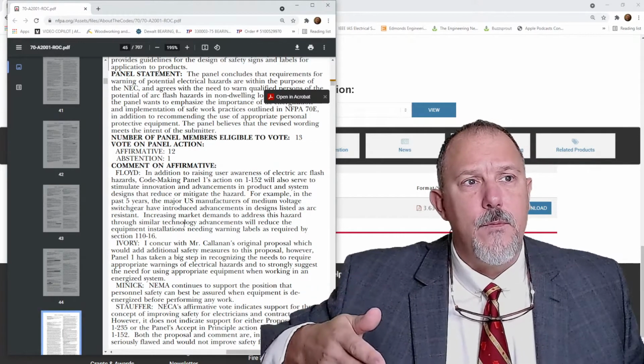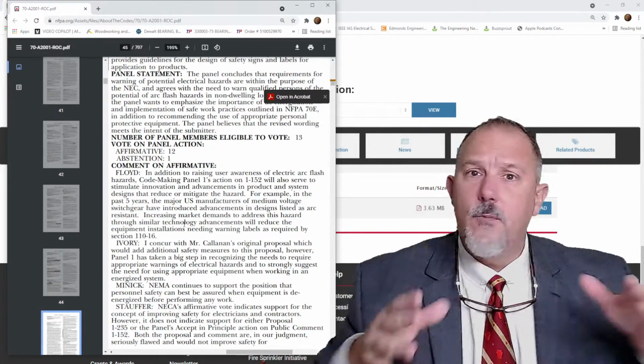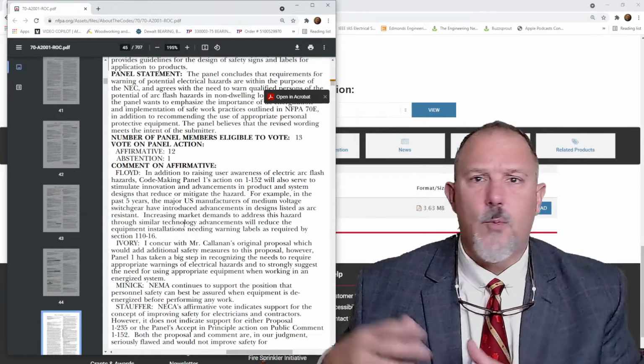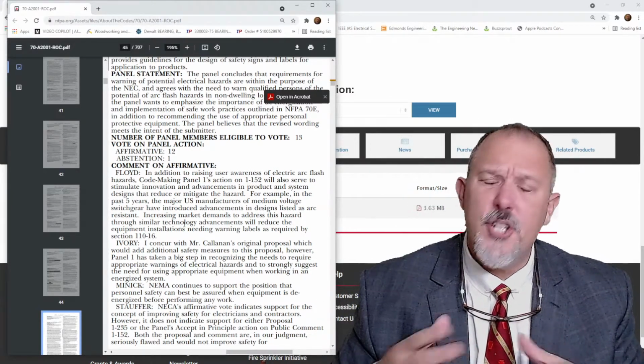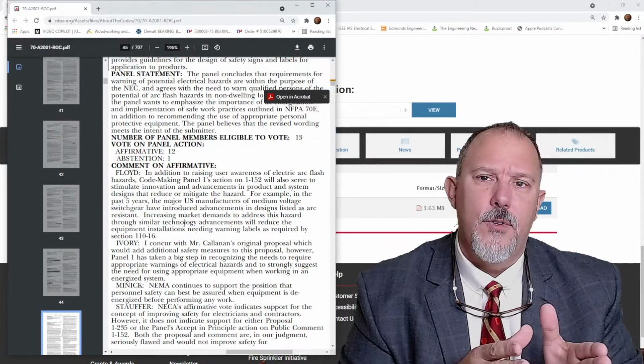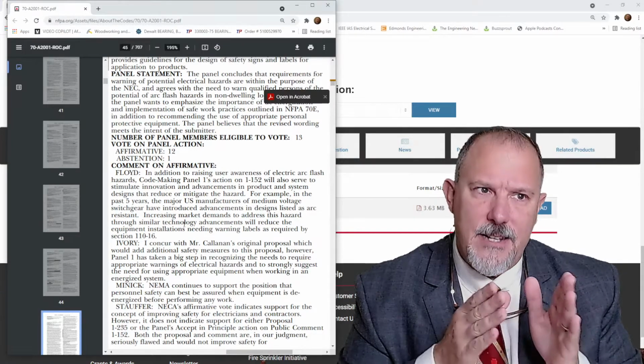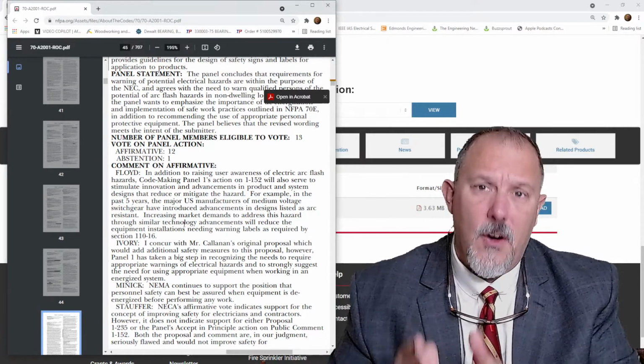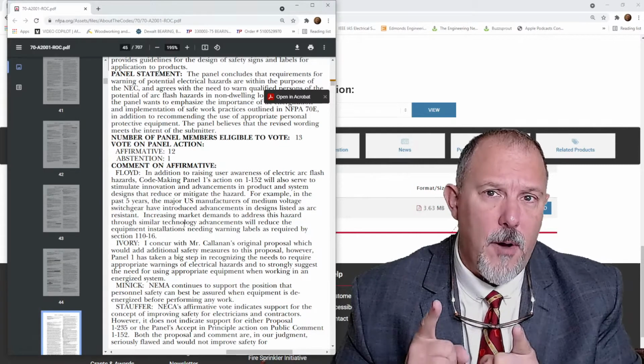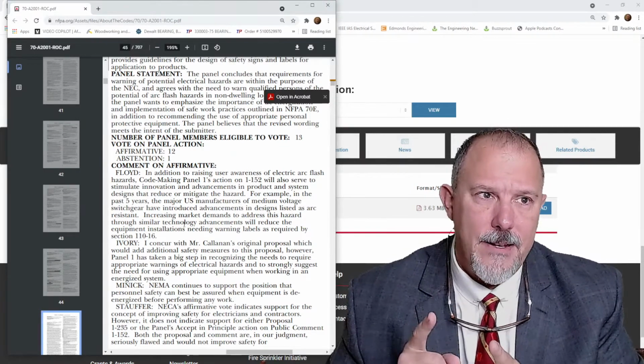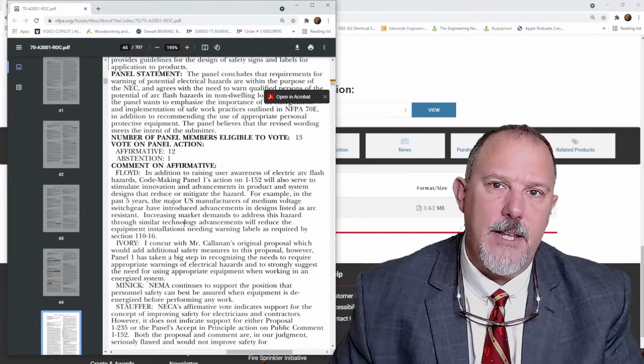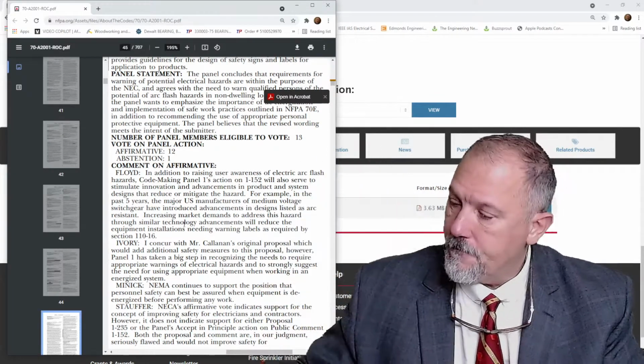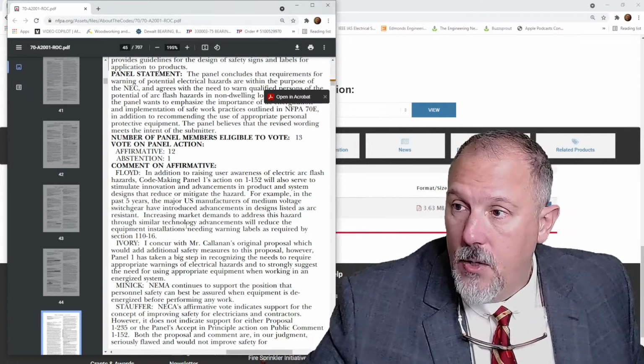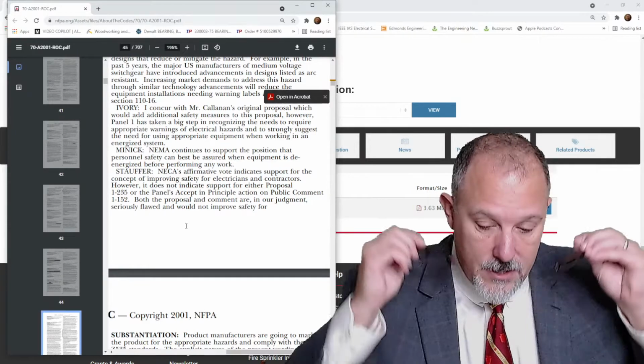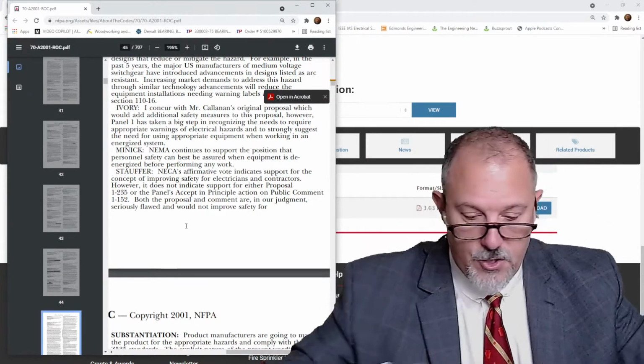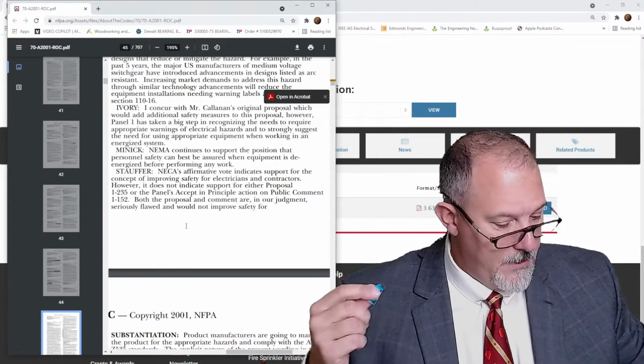We know that 240.87, 240.67. And then there are some changes in and around the six disconnect rules in the 2020 version of the National Electrical Code. So there's a lot of different changes that indirectly impact, but this one, I think, plays a significant role in the history of arc flash incident energy requirements in the National Electrical Code. Although it be only a label, it played a significant role in the development of the NEC with regard to its partnership with 70E, part of the trilogy. Okay, so now we get a better picture. So now if we looked at the 2002 version of the NEC, and we go to 110.16.